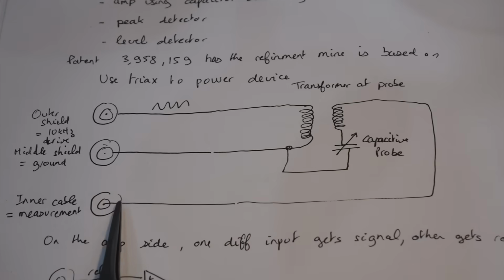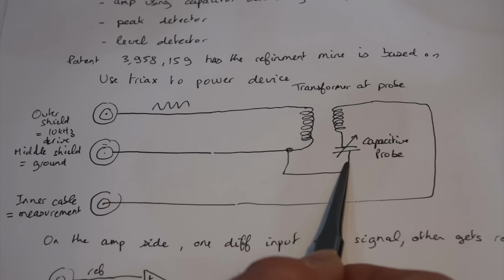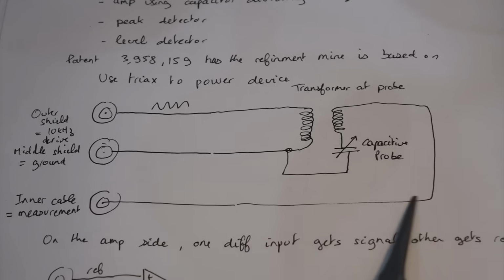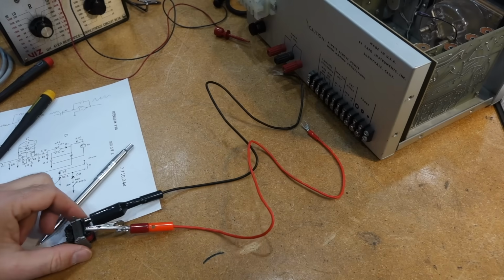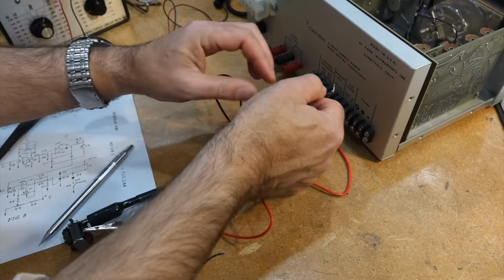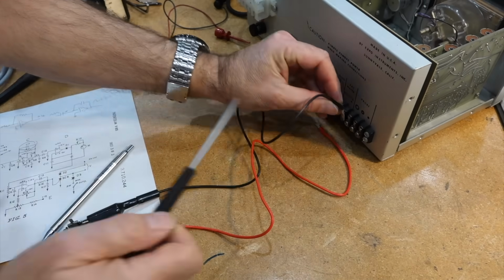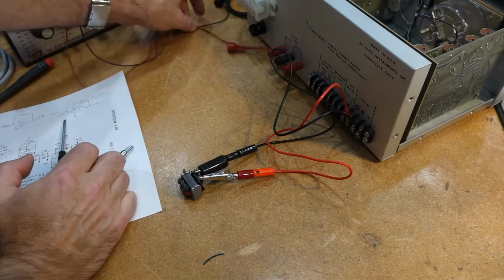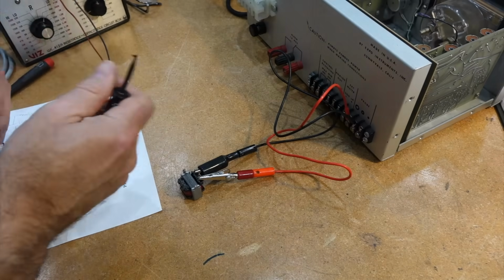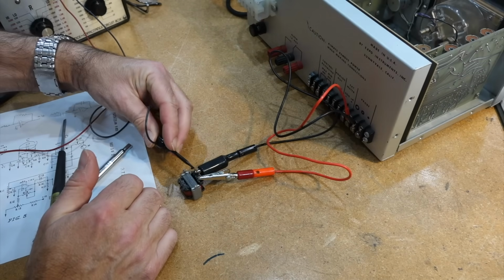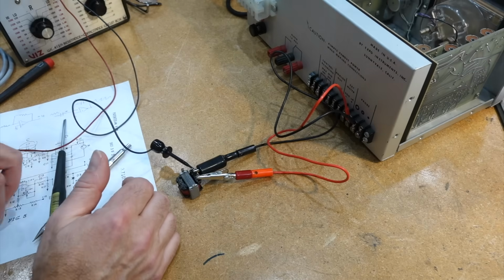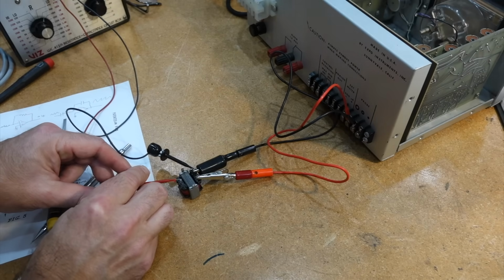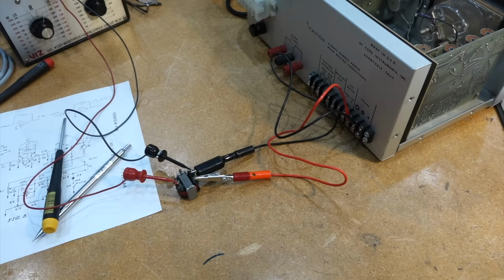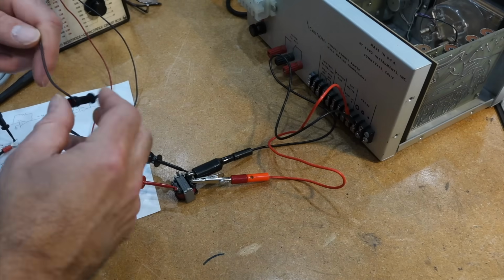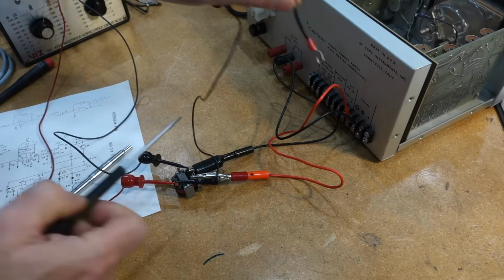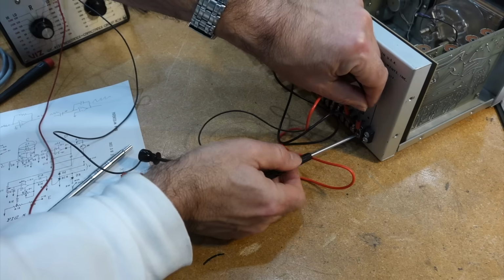It puts it in series basically. So your measurement circuit is this, the cap. This puts the signal at the end, and you measure it over here. So here is my little audio transformer, and that should be the ground pin. The capacitor should be between the ground of the excitation, so that's the outer shield of the triax, and the output of the transformer. Measurement signal comes out and goes back to the center conductor on my hieroglyphics over here.